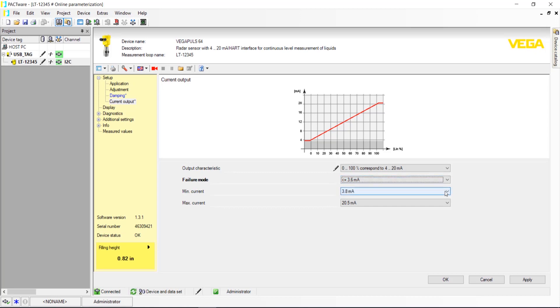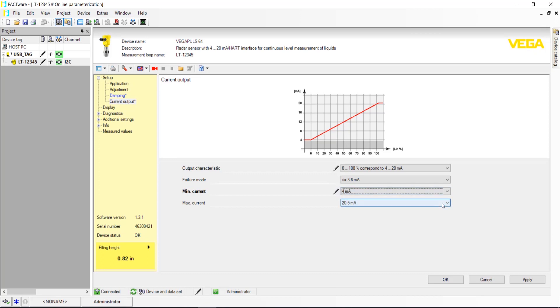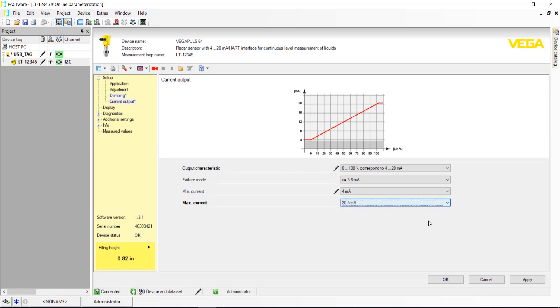For Minimum Current, the default is set to 3.8 mA, which would allow the sensor to output values less than 0%. And for Maximum Current, selecting 20.5 mA will allow the sensor to output values greater than 100% for overfill verification. After making your selections, click Apply.